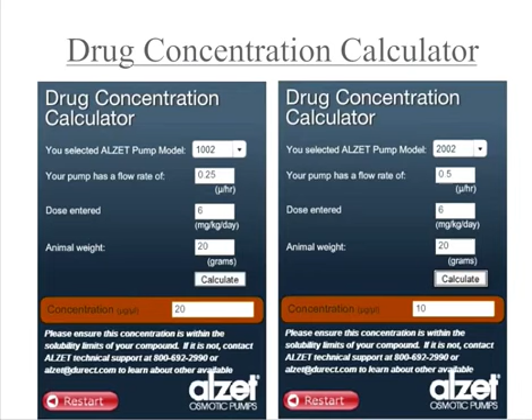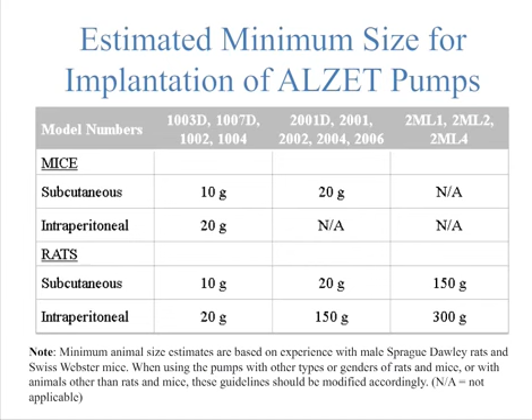Keep in mind that not all pumps can be implanted in all animals. There are different minimum weight requirements for not only the different sized pumps, but also the different sites of implantation. Those sites being subcutaneous and intraperitoneal. So for example, any 100 microliter sized pump can be implanted subcutaneously in mice weighing at least 10 grams. However, if the same 100 microliter sized pump is implanted IP, then the minimum weight requirement is 20 grams. So please keep these minimum weight requirements in mind as you're choosing the best pump for your study.